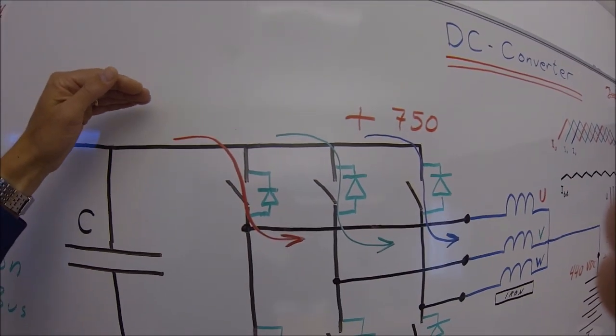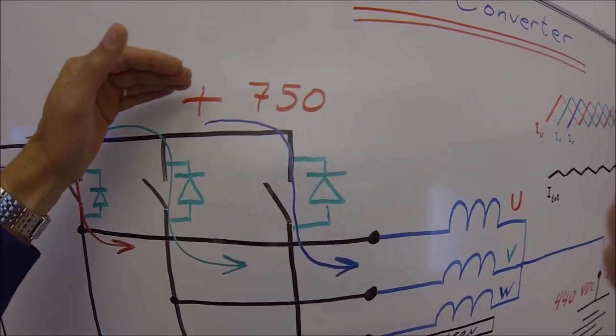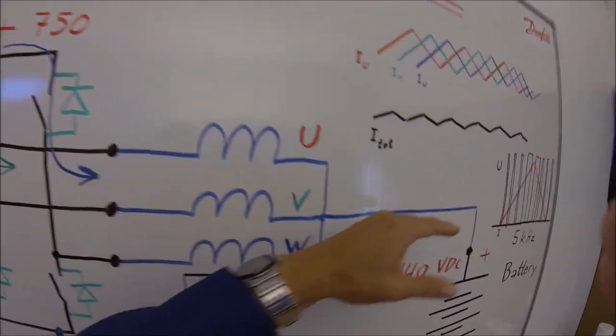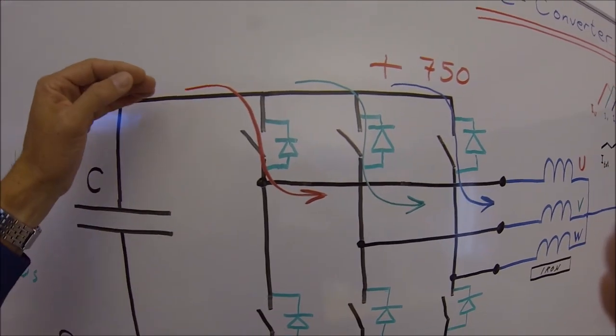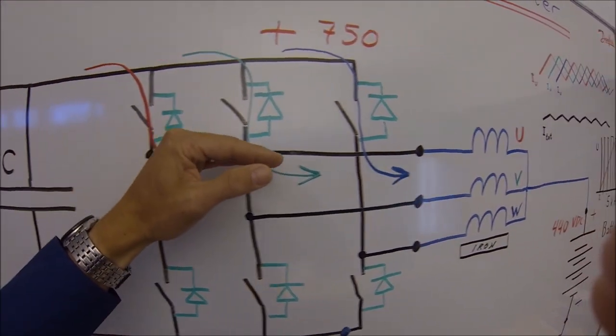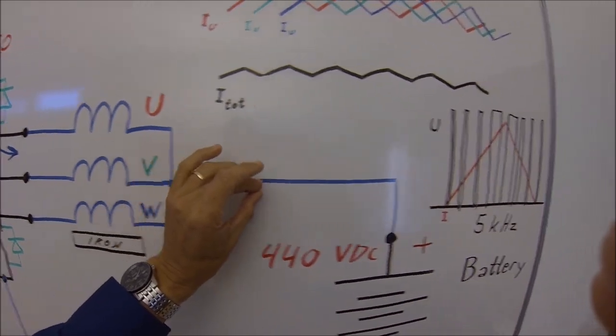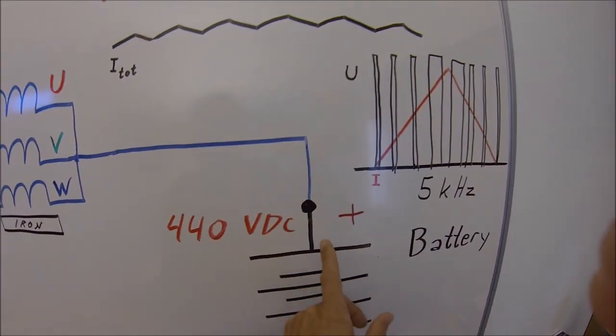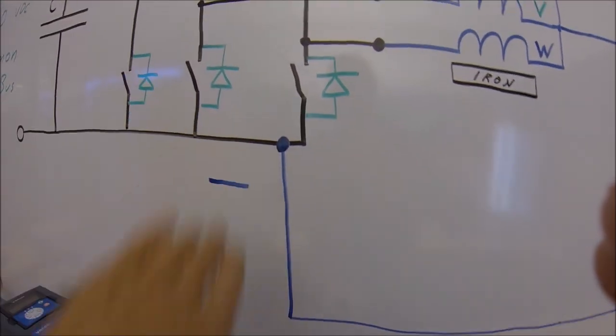When we want the current to flow from the common DC bus to the battery, the higher voltage on the common DC bus will drive this current. The IGBTs will, with pulse width modulation, source the trapeze-shaped current into the chokes. The summarization of current will go to the battery and the minus is led back to the common DC bus minus.